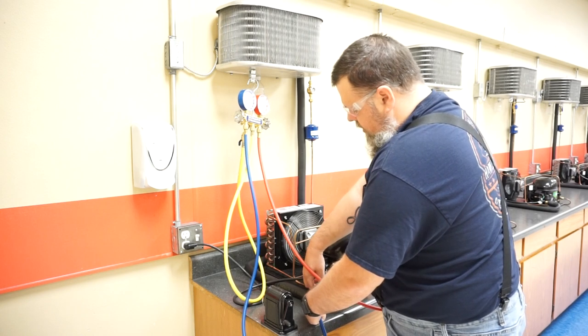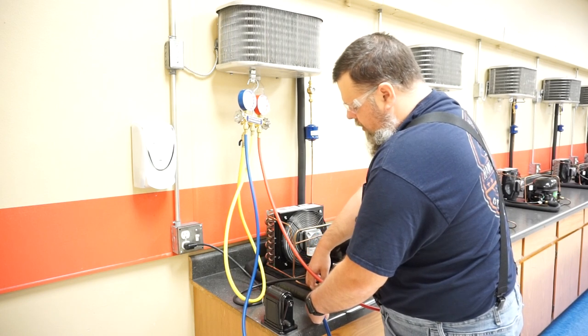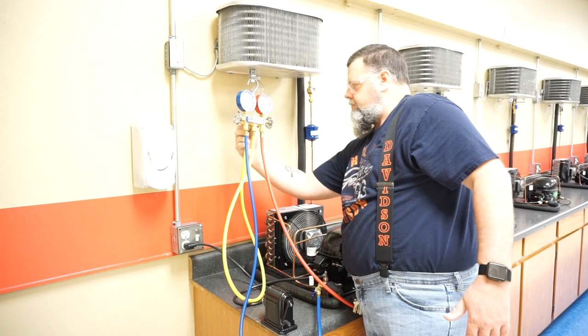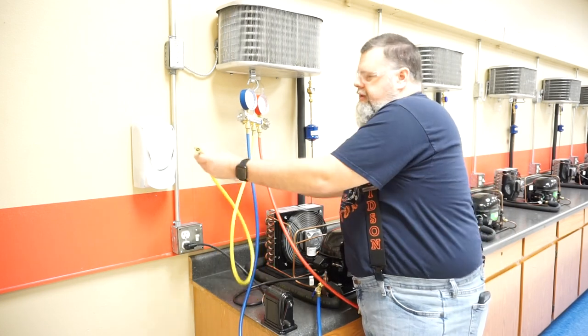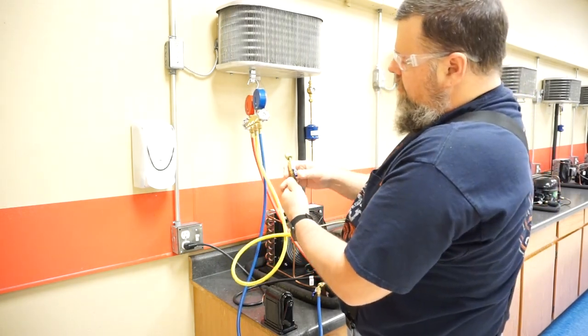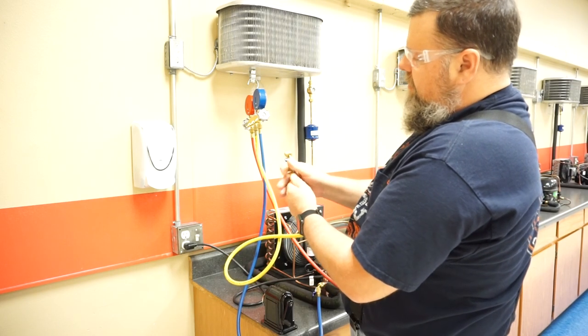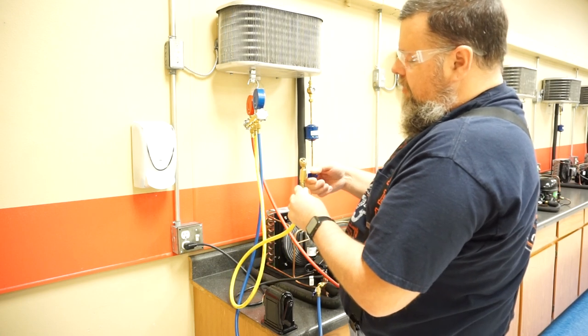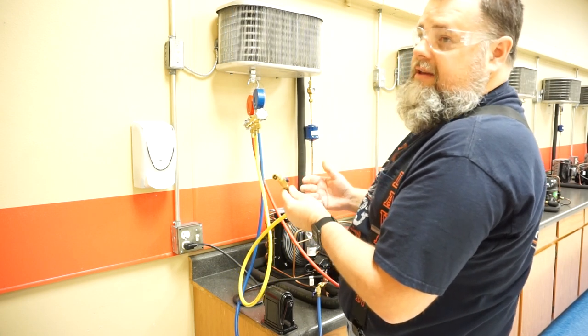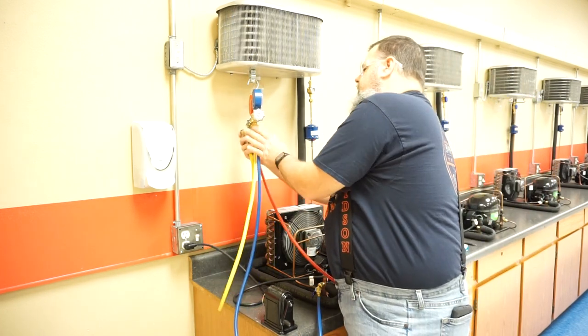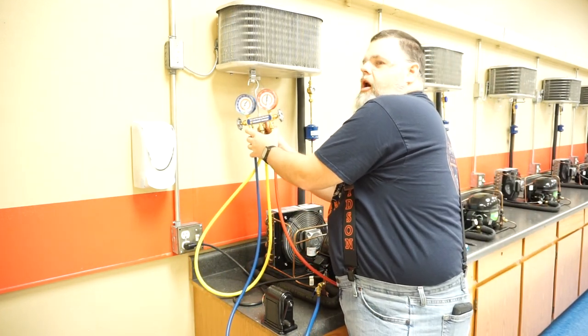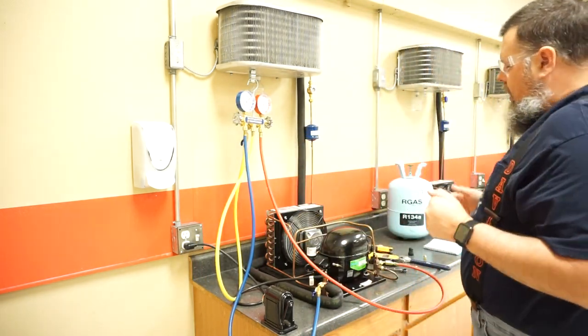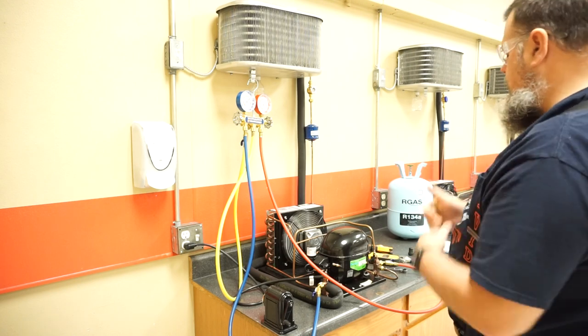Now these hoses we're using are your standard hose but they do have low loss fittings on them. Low loss fitting I will show you before I go any further. Your low loss fitting looks like this and you can close and open that line with this. It's very good to have when they're already built in like this. This is a ball valve so it really doesn't go bad that easy. These are manual instead of automatic. You can get automatic ones which open and close for you.